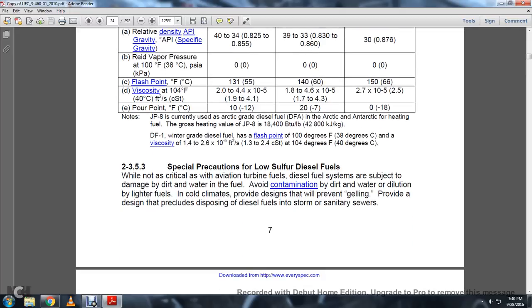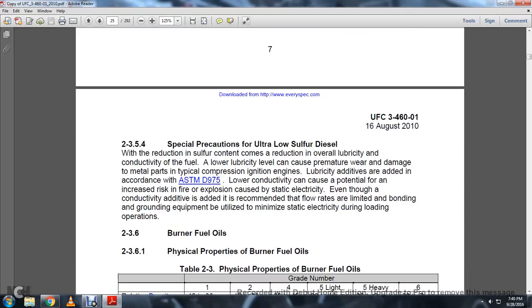2.3.5.3 Special precautions for low sulfur diesel fuels. Not as critical as for aviation turbine fuels. Diesel fuels are subject to damage by dirt and water in the fuel. Avoid contamination by dirt and water, and dilution by lighter fuels in cold climates. Provide a design to prevent gelling, and a design that precludes disposing of diesel fuels in storm and sanitary sewers.